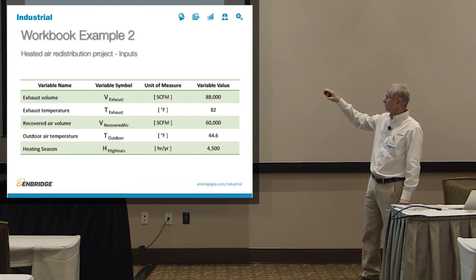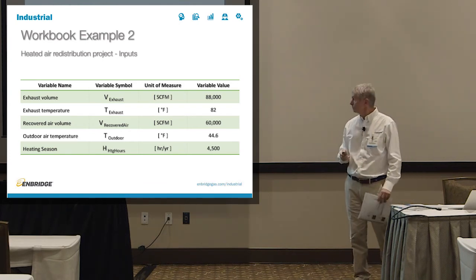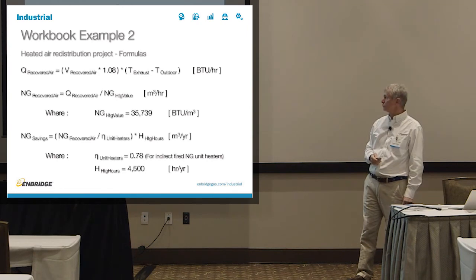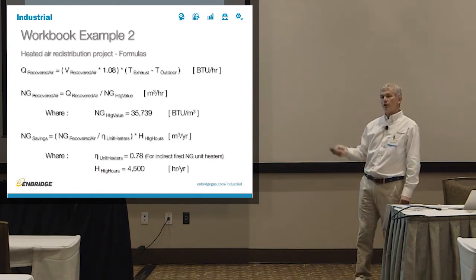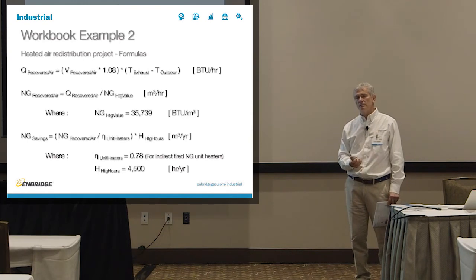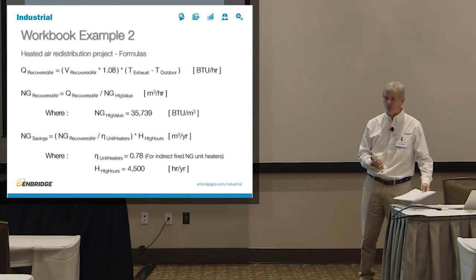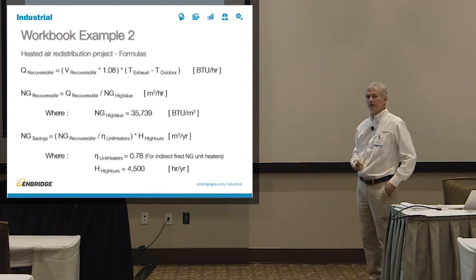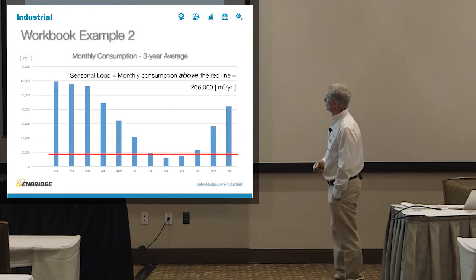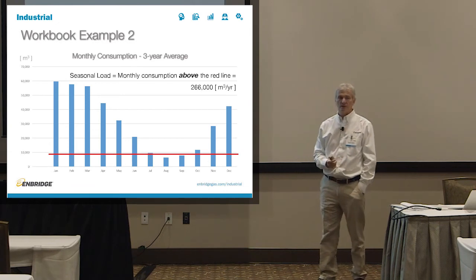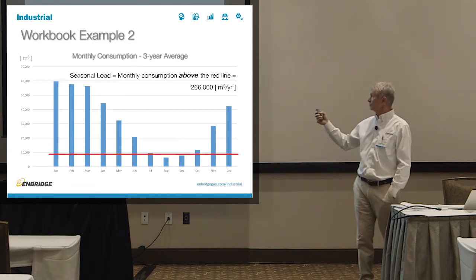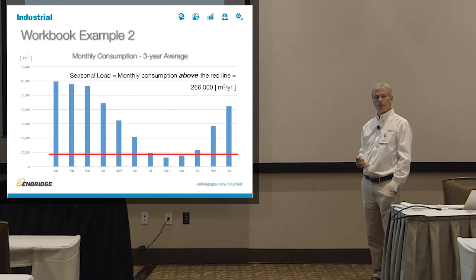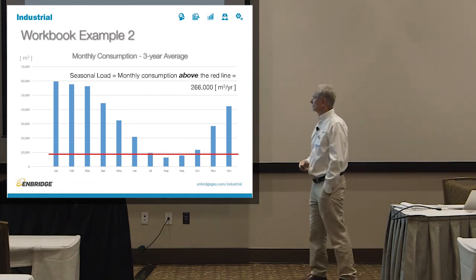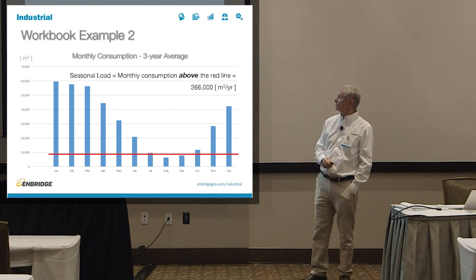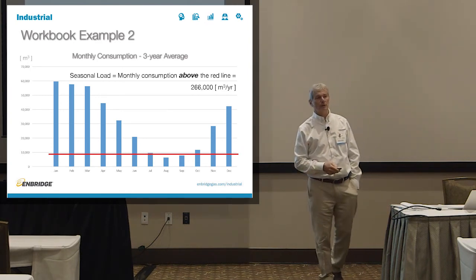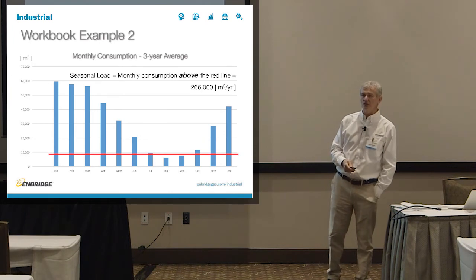So these are the inputs. Again, there's a symbol there, units of measure. And these are the formulas that we will use to do so. We'll use 4,500 hours of the heating season in this particular case, because that's typically what your facility will see in a year. And we'll add another twist here. We will say that this facility has this type of monthly consumption profile. So over the year, we will say they use 266,000 cubic meters of natural gas for heating of the facility.